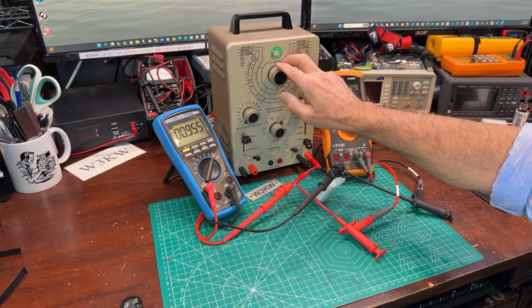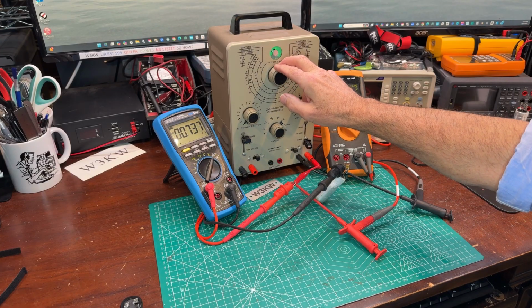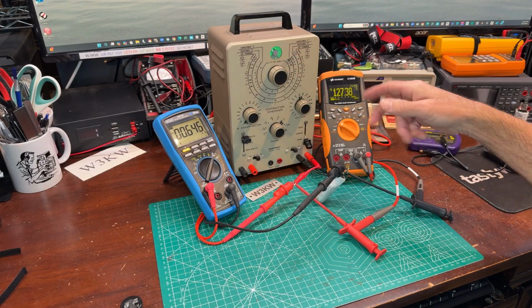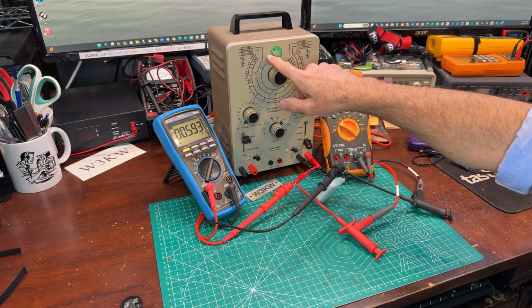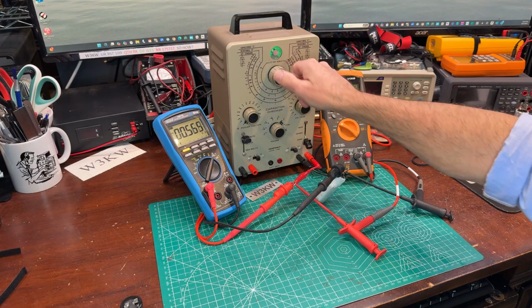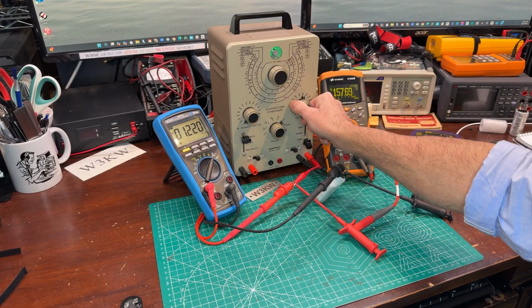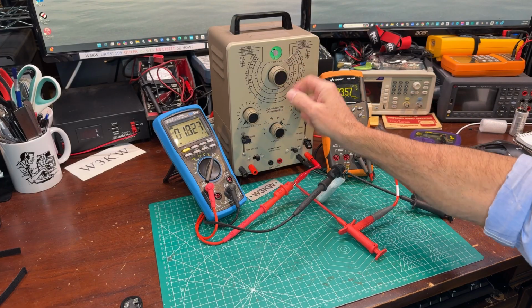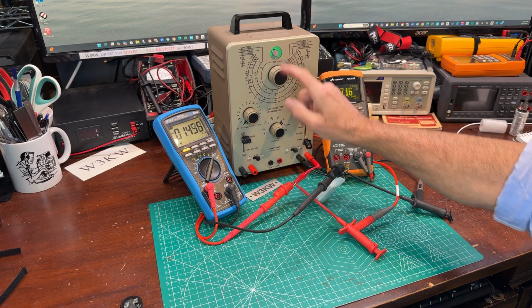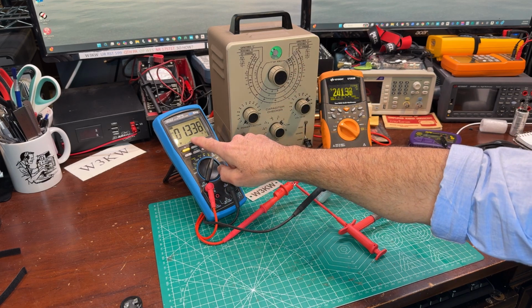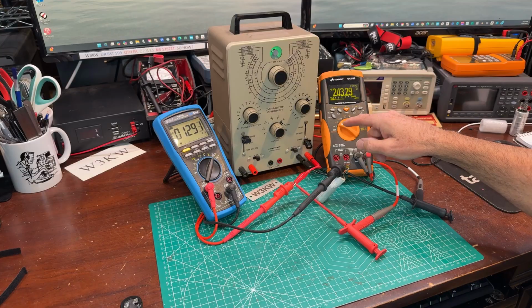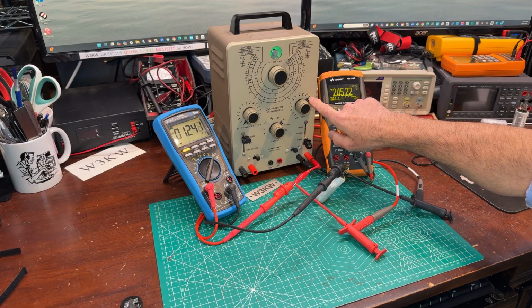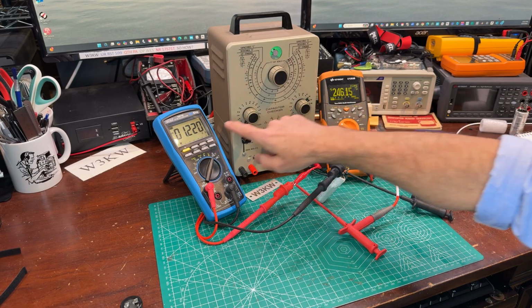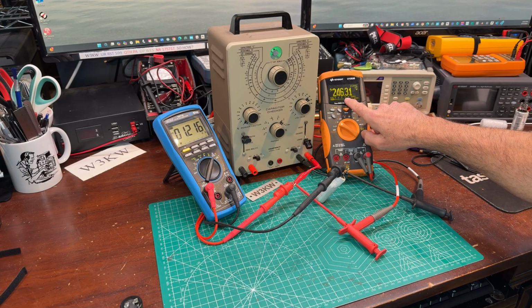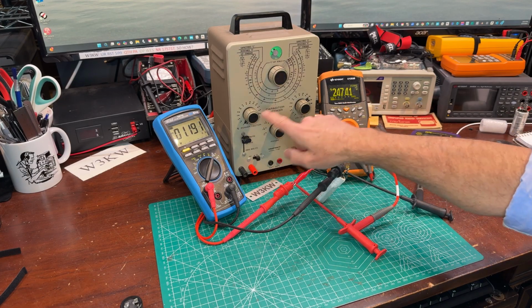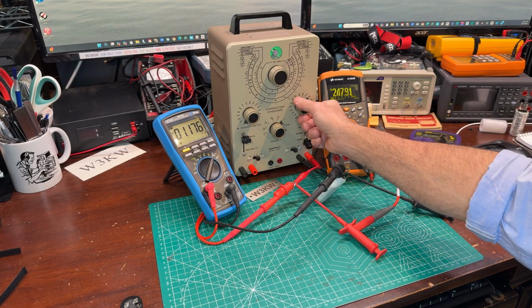Remember, when the window closes, it's presenting DC leakage, and as the capacitor loads up, the window will open, indicating that it's okay. So there's 300 volts. It's struggling to hold 300 volts. You can see we're already at 1.3 milliamps of current, and though the meter's set to 300 volts, that's already a 50 volt load on this circuit.